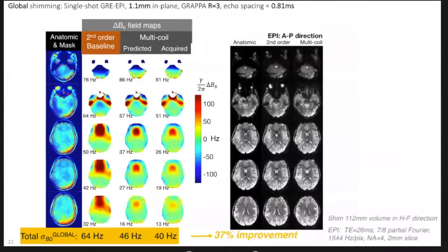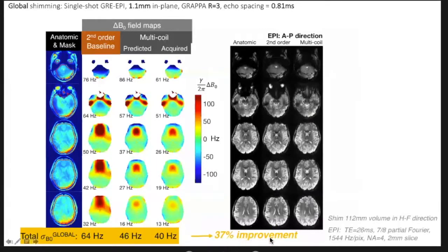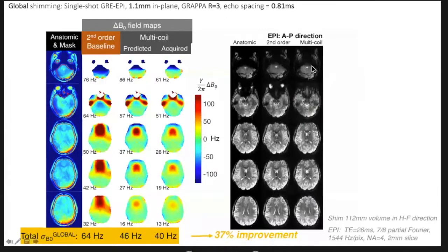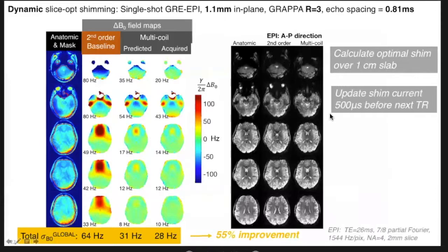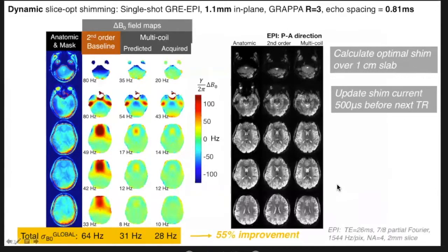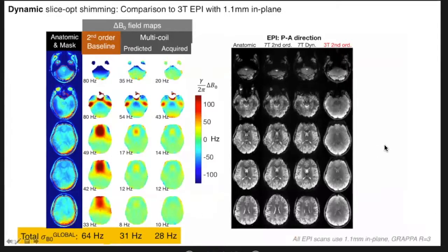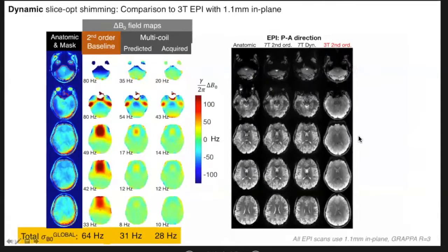So what does this do for the distortion? Here's the field maps for global shimming, and here is the distortion. This is a contrast-matched, undistorted GRE. This is the EPI, AP and PA phase-encoded with the second-order shim and the multi-coil. And you can see ventricles aren't moving around as much. In the deep brain, the medulla and the cervical spine don't move as much. It's a noticeable improvement. But where you really get the payoff is with dynamic shimming. Here, we shim each slice optimally so it's easier to flatten out the shim. You can see the field maps also look better. And just for comparison, here's the same protocol run at 3T, the same echo spacing, same grappa factor. And we're almost down to the distortion that we would get on a garden variety 3T scan. So we're pretty excited about this.